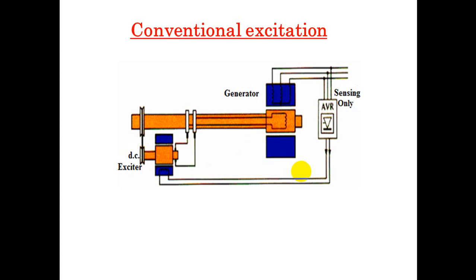Enough to have a voltage output of the main generator. The AVR shown in this figure can start to have a current to help the remnant field, and the loop keeps increasing up the regulating values. So that's all about the conventional excitation system.